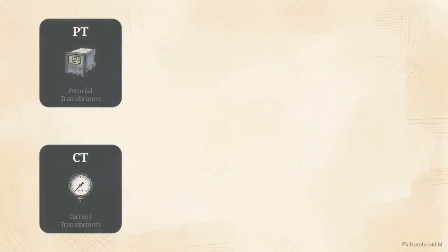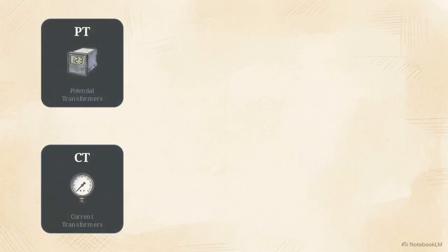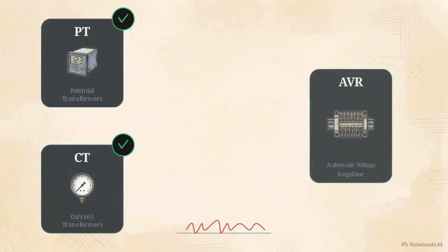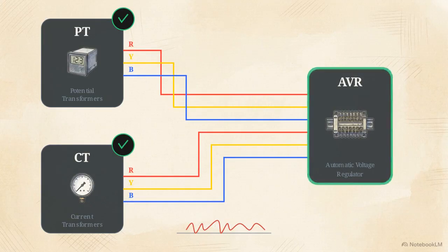Next is a strict signal readiness audit. You must confirm that all baseline tests for the potential transformers and current transformers are signed off.